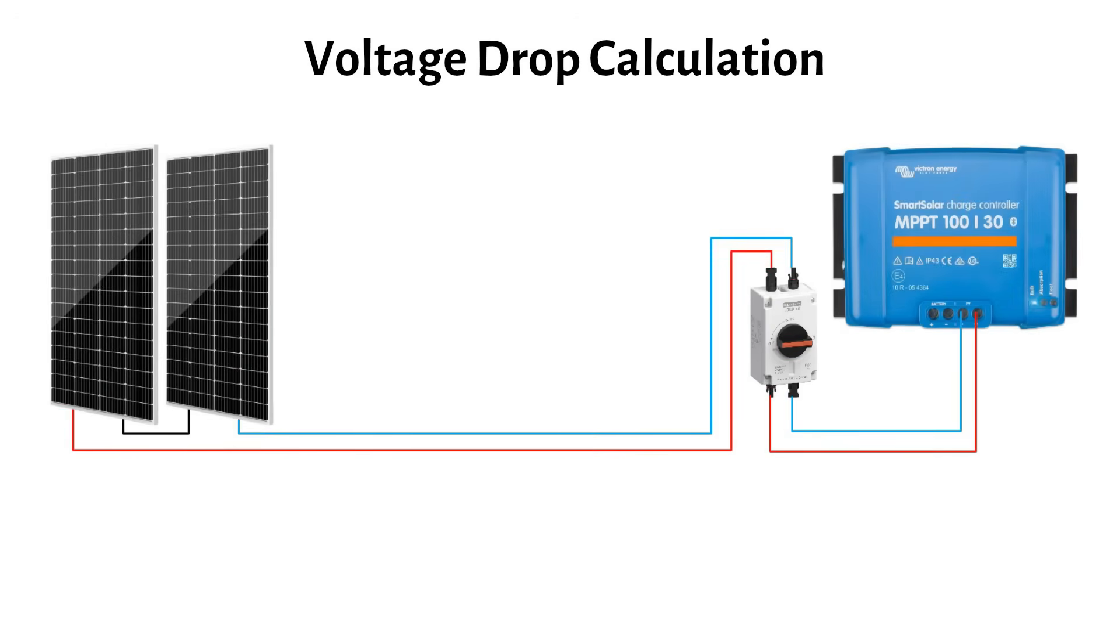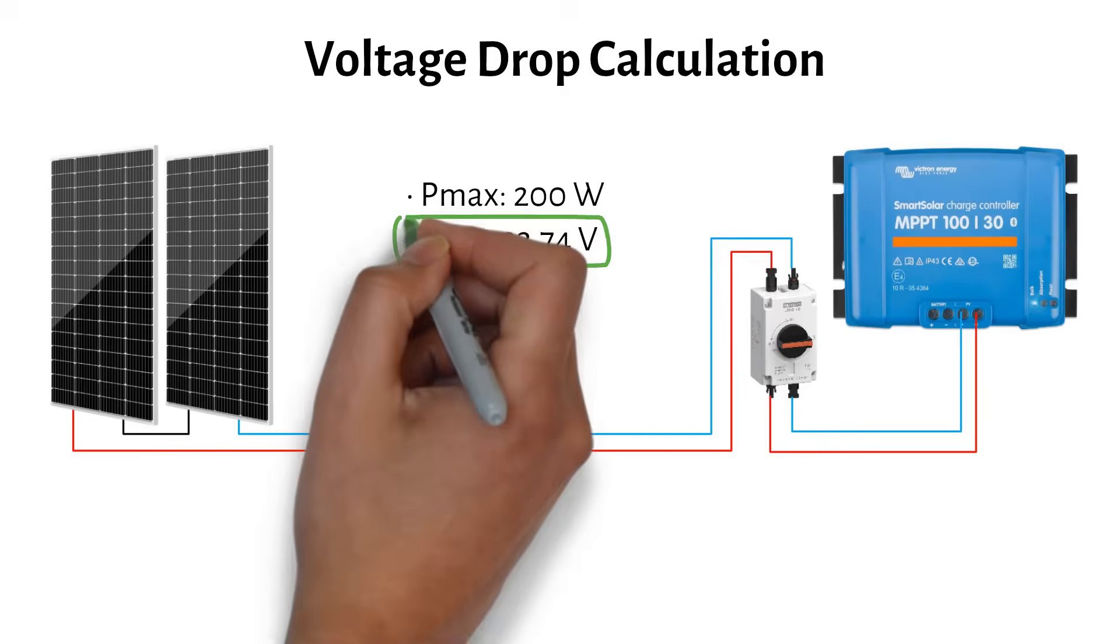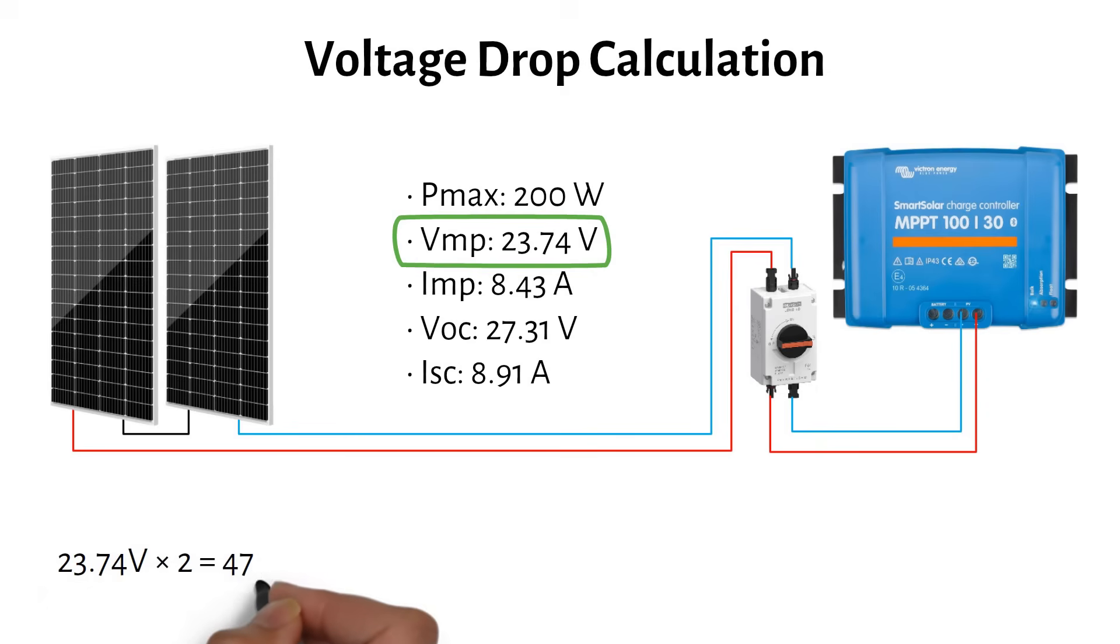So let's start by gathering all the necessary information to calculate it. First, we need the string voltage and the cable length. Remember the solar panel specifications? Two panels in series means the working voltage or VMP is multiplied by two panels. This gives us 47.5 volts.